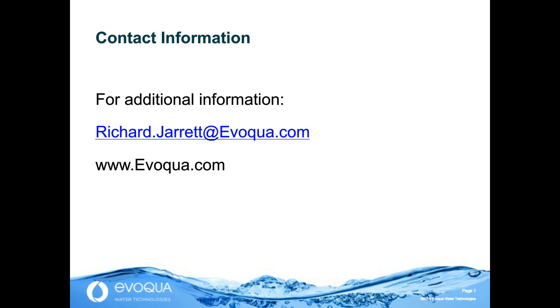In Europe, the EMA guide says to consider two-pass or product-staged RO. So I would say that it should be considered. I don't see it as a regulatory requirement. And I did point out cases where the process could require it, that it could be a high TDS water or a critical quality attribute. There could be a very low level, well below USP, EP limits, that might drive two-pass.